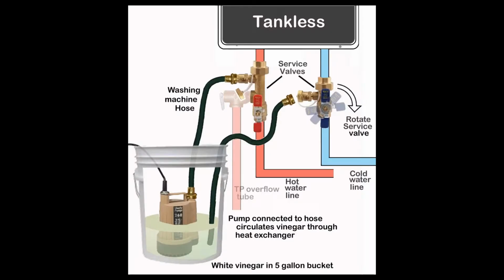Now, underneath the tankless water heater, you should see ports. Now, these ports are not for show. These ports are for the licensed master plumber to clean the system out once a year, or annually. They're going to use some white vinegar in a 5-gallon bucket. They're going to pump the connected hoses, circulate vinegar through the heat exchanger. These are basically washer hoses.